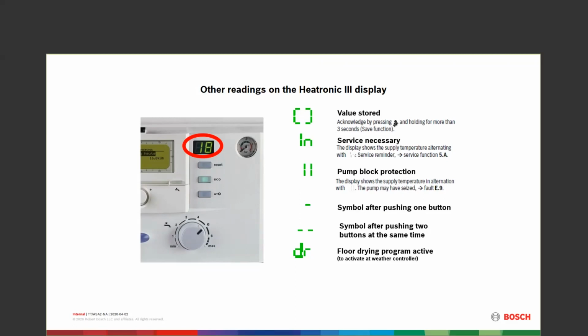Next one is the IN, showing us that we have a service that's due, set by whatever interval you want to set. Generally, 1 year is a nice interval. A customer will go down and see IN. He either knows that he's got to call you for service because that's what it is, or feels that something else is wrong. So if he's seen something different on there that he hasn't seen before, he's going to call you. These boilers should only need to be serviced or taken apart and cleaned about once every 5 years.